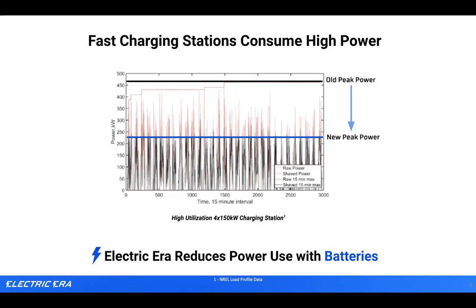So there's this very unhealthy balance between the grid infrastructure that has been installed, and needs to be installed, to support these very infrequently used and short duration load transients. That's the first principles rationale for why this is a major problem. The economic math behind all this is ultimately that a grid operator charges this DC charging station as a function of that peak power installation and how much they use in a given month.